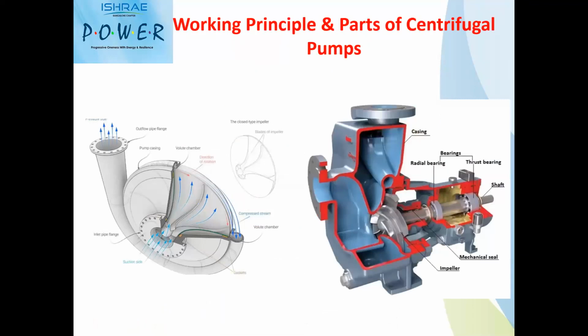Working principle of a centrifugal pump, as I told, all of our HVAC pumps are centrifugal pumps, where the liquid is transferred from one level to the other level by centrifugal action. So there will be a rotating element. This is the shaft wherein the impeller is mounted. This is the impeller, and water enters from the eye of the impeller, and the impeller will have vanes which will guide the water since it is moving at a high RPM like 1450 or 2900 RPM. By the centrifugal action created from the eye of the impeller, water moves towards the vanes and it is guided through the volute of the pump. When water enters the volute, it is called the volute as well as the diffuser. By centrifugal action, water is pressurized through the volute and guided to the exit of the pump, wherein it will have pressurized water which will displace from one place to the other place.